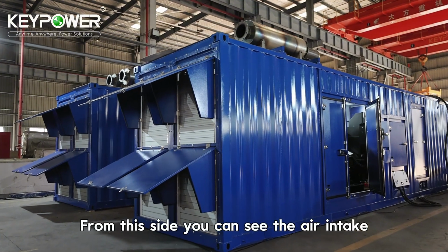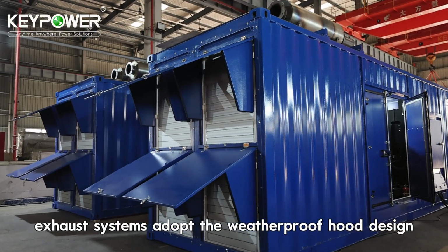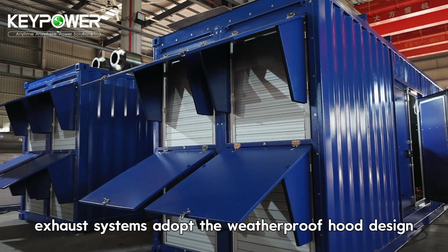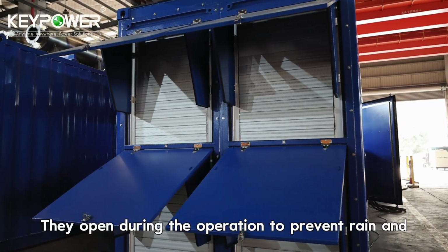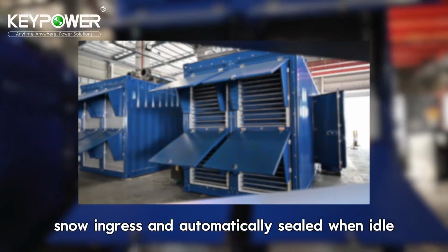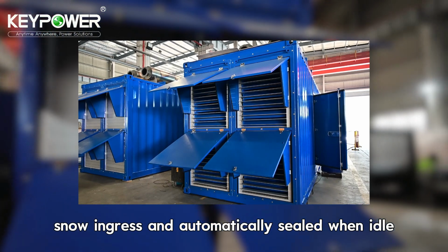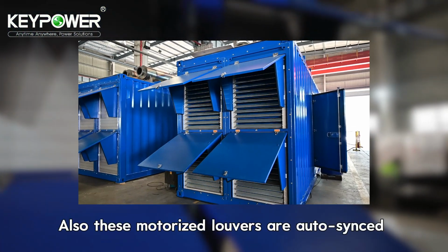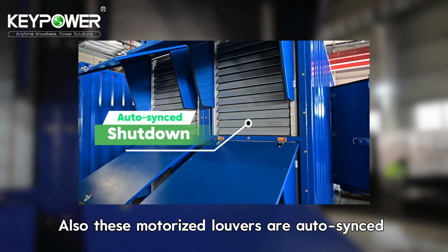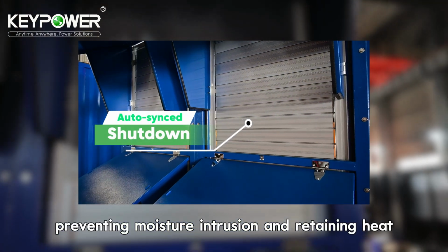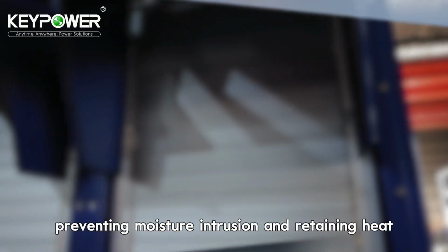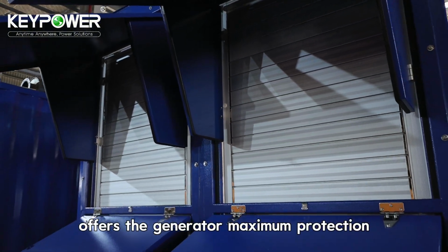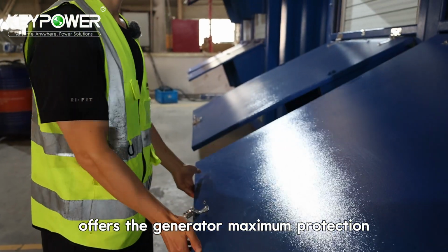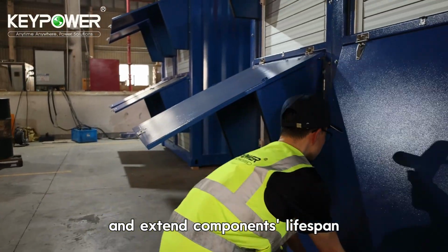From this side, you can see the air intake and exhaust systems adopt the weatherproof hood design. They open during operation to prevent rain and snow ingress and are automatically sealed when idle. Also, these motorized louvers are auto-synced with the generator, preventing moisture intrusion and retaining heat. All the design offers the generator maximum protection and extends the components' lifespan.